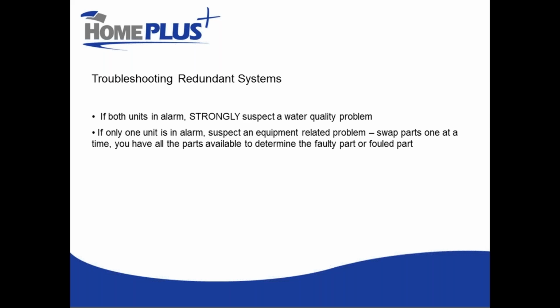If both units are in alarm and doing exactly the same sort of alarm condition, or if you have 3 units, all 3 of them, you can strongly suspect that the problem is related to source water quality. It could potentially be related to lack of maintenance, i.e. sleeve cleaning on all 3 units, or both units, or whatever the case may be. But it's probably more likely a water supply issue.